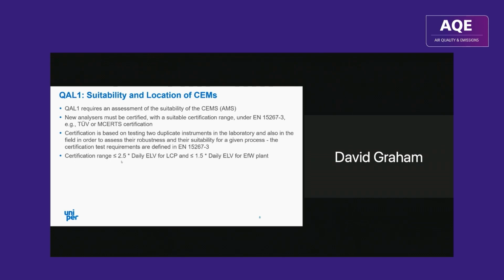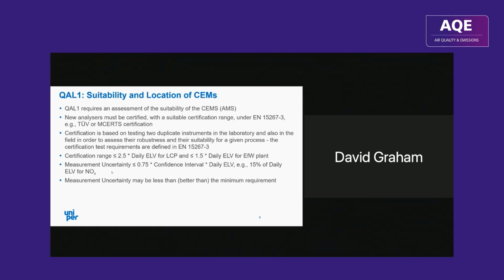The certification range must be less than 2.5 times the daily limit for a large combustion plant and less than 1.5 times for energy from waste plant. And additionally, as Rod mentioned, the measurement uncertainty at certification must be less than 3/4 of the confidence interval. So for NOx with a confidence interval of 20%, at certification, the instrument must be better than 15% of the daily ELV. But of course, measurement uncertainty on a certificate may be less than or better than that minimum requirement.